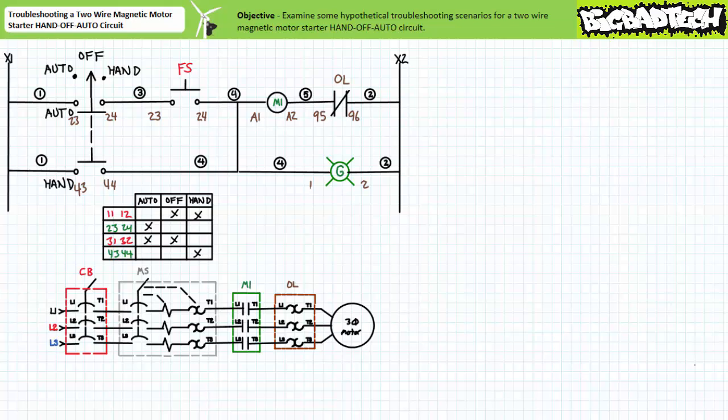Recall our two-wire magnetic motor starter hand-off auto circuit used a maintained contact three position selector switch and a push button standing in for a float switch to control the operation of a motor driven pump. An operator could place the circuit in one of three modes: Auto, where the simulated float switch automatically controls the motor; Hand, which turns the motor on whether the simulated float switch calls for it or not; or Off, which halts the motor even if the simulated float switch closes.